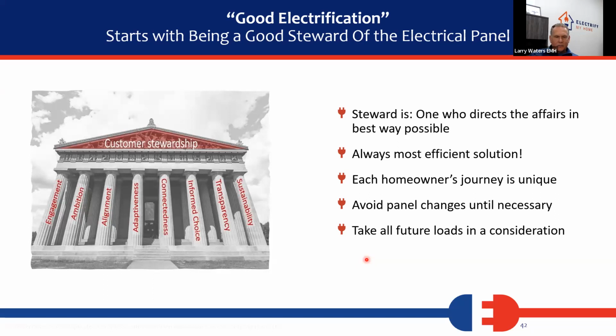We've electrified complete houses on 100 amps that are probably never going to get solar. But because we did it with low energy appliances, their utility bills are not that bad. They're less than they were when they were using gas heat. So they're happy with that. And they still have that same 100 amp panel. They didn't need a panel upgrade, so they didn't cause impact in the neighborhood by getting a larger panel that wasn't required.